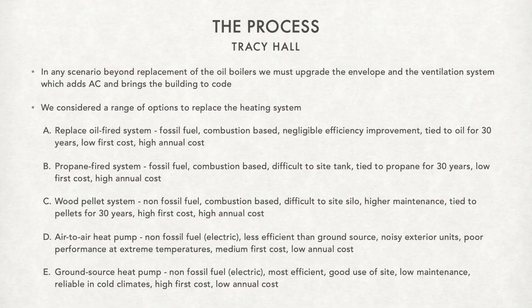The advantage is there will be nothing visible from the outside—those compressors would go away. The ground source system is all under the parking lot, so it wouldn't be visible, and it's totally silent, just circulation of water underground. It's the most efficient system and a good use of the site, meaning nothing visible from outside, no noise or exhaust. It's a very low maintenance system because all you're doing is circulating water outside the building, and it's reliable in extreme temperatures. It's a little more expensive to build, but it has by far the lowest annual cost because it's the most efficient. Over a life cycle, it's arguably the cheapest.